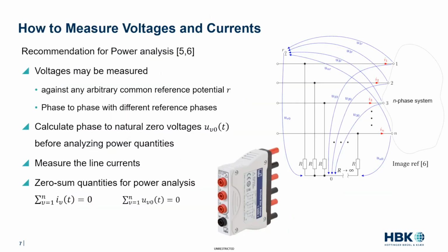And therefore, I would like to show you that based on a very general diagram topology. We have here an N-phase system. And in practical measurements, this N-phase system could, for example, be an electric machine. It could be an inverter. It could be the combination of both. And as you know, there are three-phase machines, multi-phase machines. So in general, you have a certain number of conductors which are connected to that system where you want to calculate the power. And in order to do correct power calculation, all conductors connected to the system, but also contributing to energy transfer, should be considered for power calculation.